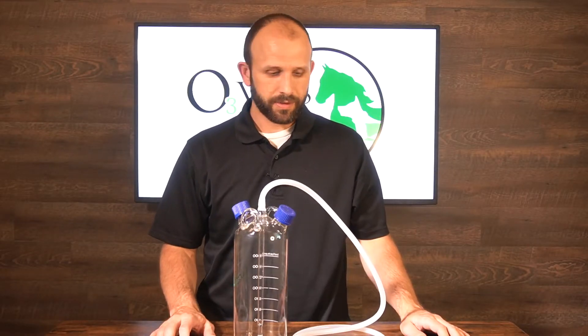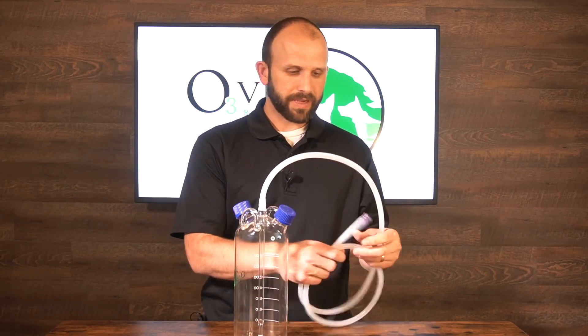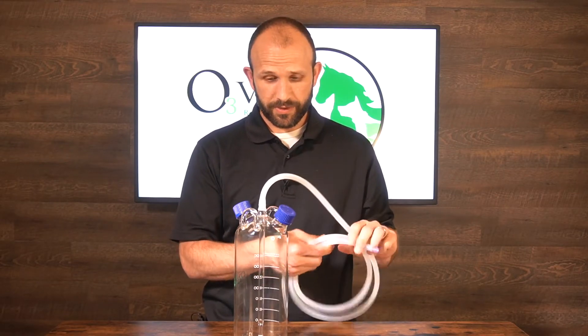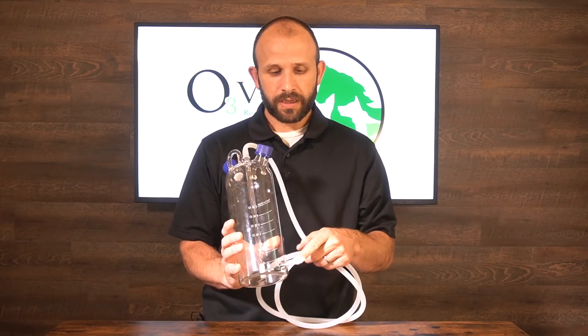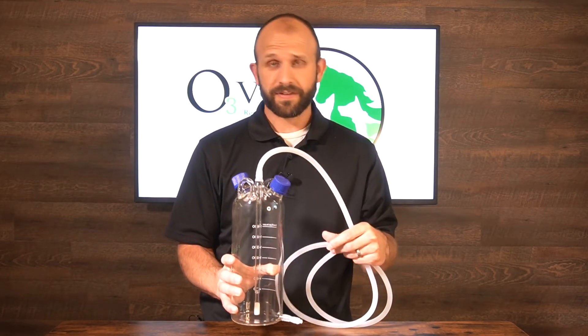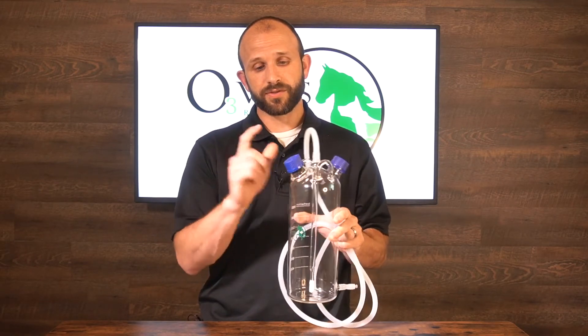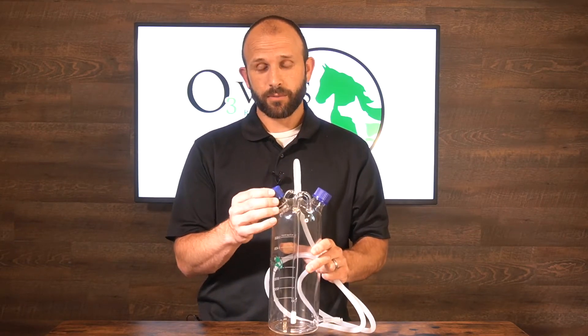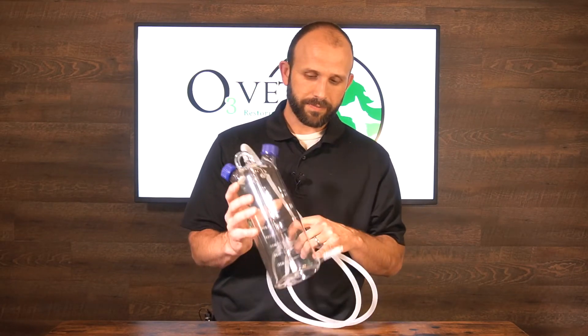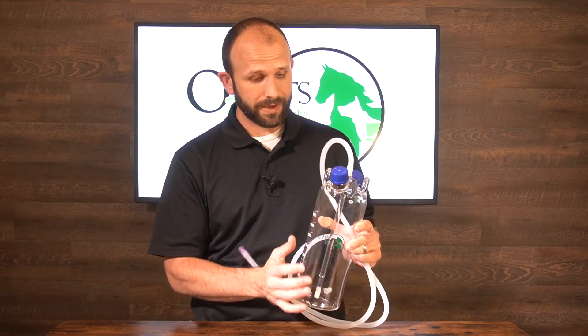This is our veterinary fluid bubbler. It comes with really thick silicone tubing to minimize any kinking. It has a spin luer lock at the end made from ozone-resistant materials. We have fluid egress at the bottom of the bubbler to make it easier to get fluids out instead of having to draw them through the top. We also have a destruct integrated into this unit which neutralizes excess ozone — that's the exhaust for that. There's a micro bubbler diffuser stone in the bottom and graduated lines that tell you how much fluid you have in the bubbler.